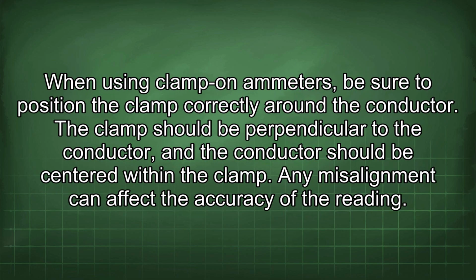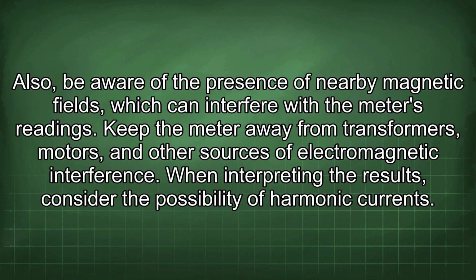When using clamp-on ammeters, be sure to position the clamp correctly around the conductor. The clamp should be perpendicular to the conductor, and the conductor should be centered within the clamp. Any misalignment can affect the accuracy of the reading. Also, be aware of the presence of nearby magnetic fields, which can interfere with the meter's readings. Keep the meter away from transformers, motors, and other sources of electromagnetic interference.